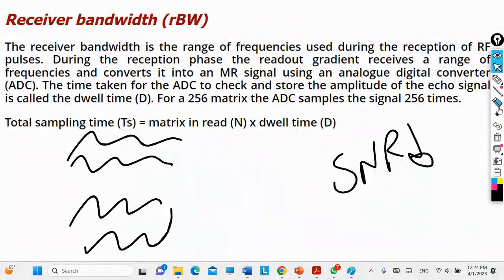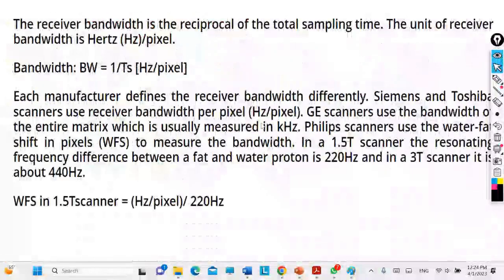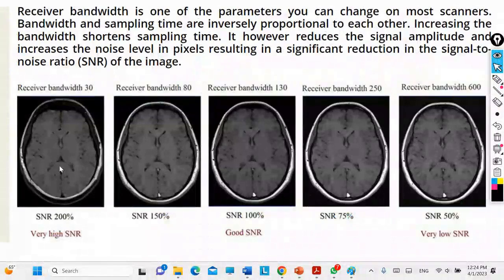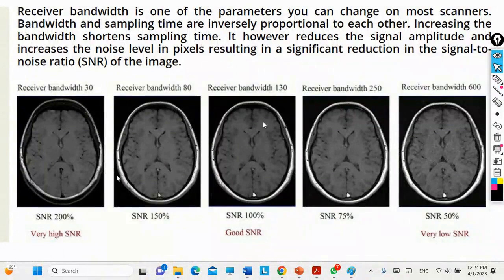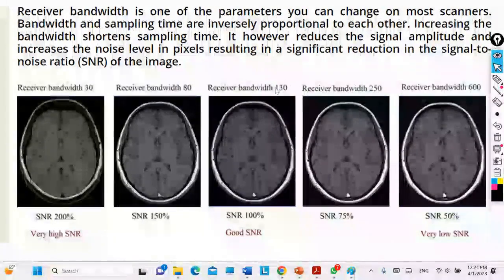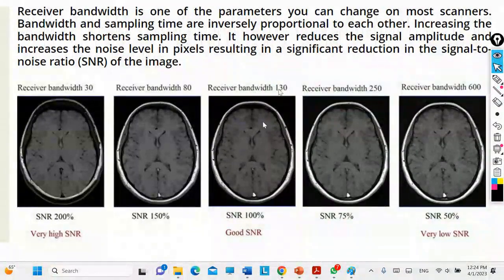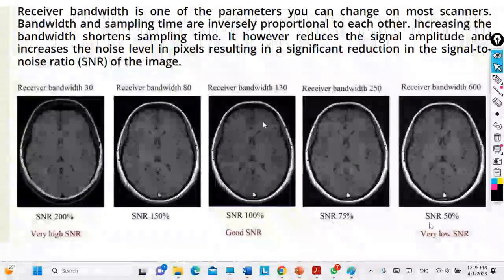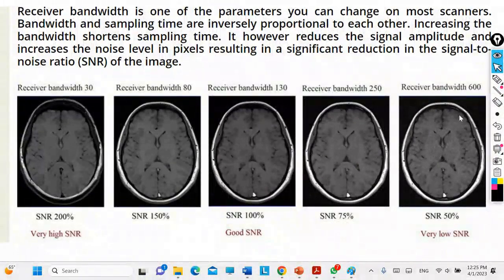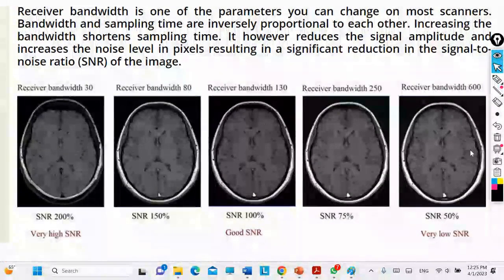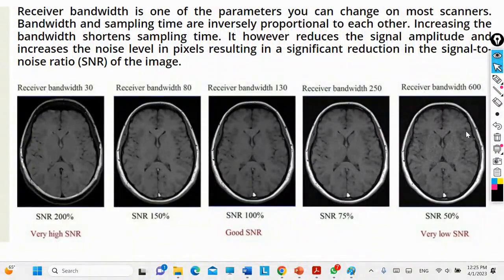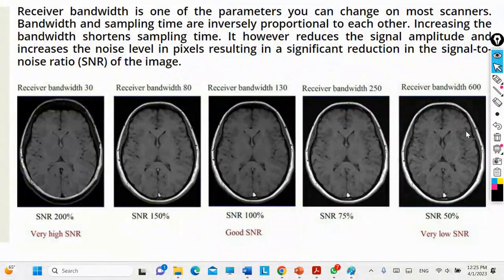For example, with a receiver bandwidth set to 30 the SNR is 200, which is large. If you increase the receiver bandwidth, the SNR starts to decrease — lower and lower — until the image becomes very grainy. So increasing the receiver bandwidth gives you a noisier image, and if it increases too much the image quality degrades significantly.